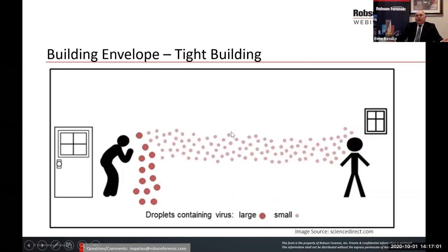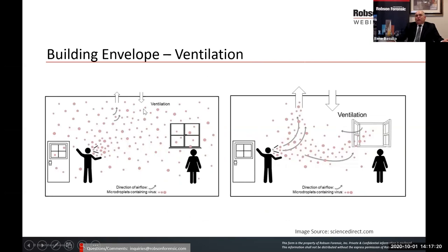So what happens when we have that type of building? You're stuck with whatever you put into the building. So in the particular case when you're looking at droplets containing viruses, whether they be large or small, they will tend to linger in the space and will concentrate within this occupied space. So with ventilation, even if it's inadequate, you do get a little bit of circulation of that. You get a little bit of dilution. But with adequate ventilation, you do get a lot more dilution of not only the virus contaminants or any pathogens, but you get a reduction in any contaminants within the building, any allergens or any VOCs within the building. You'll get that with adequate ventilation.